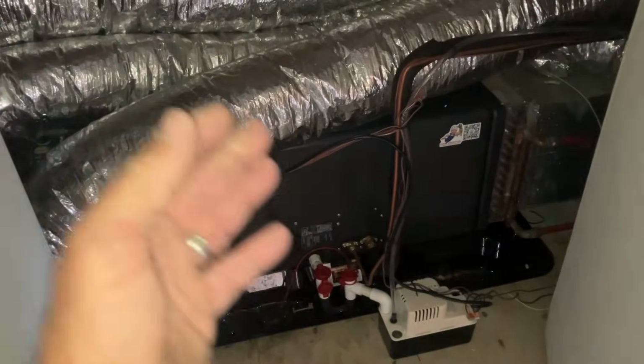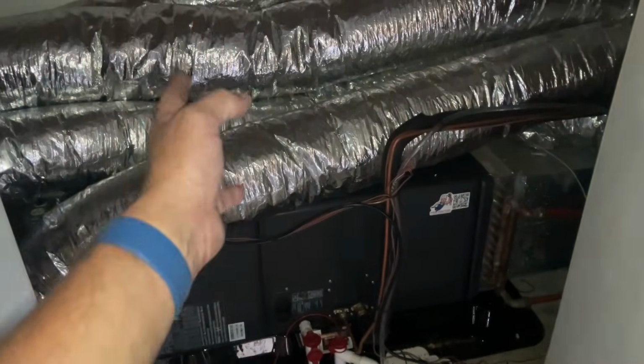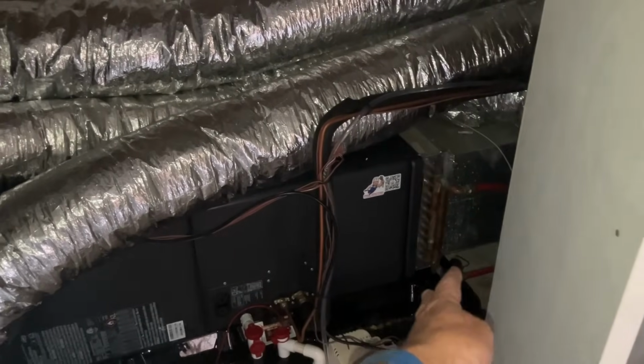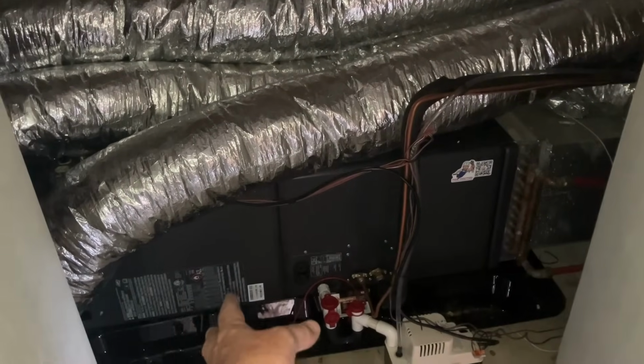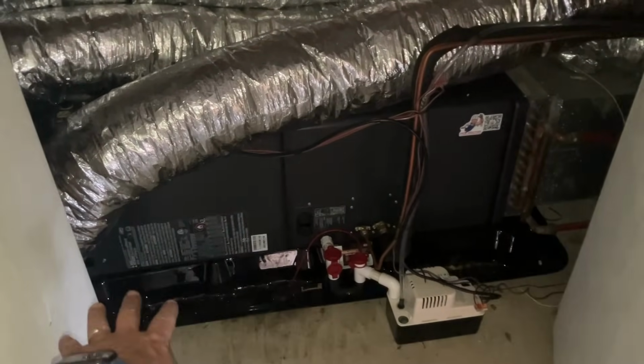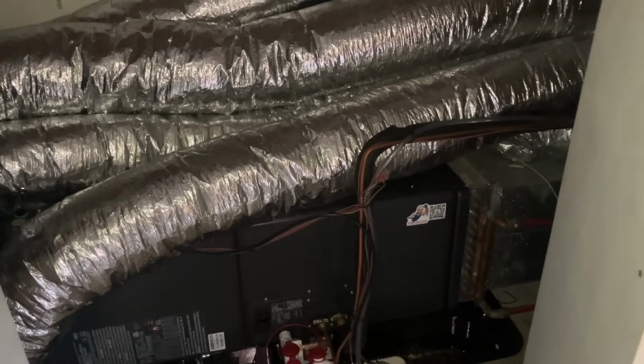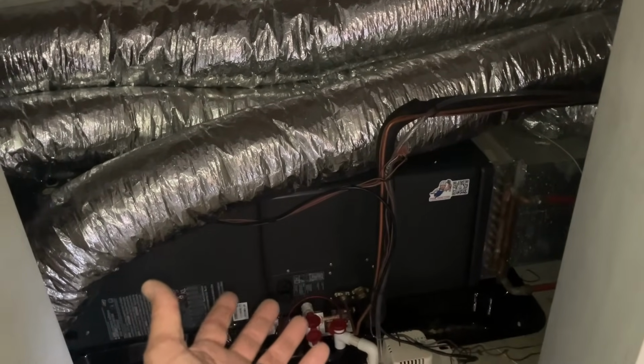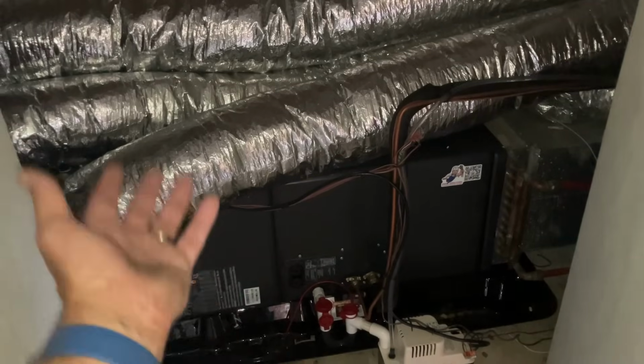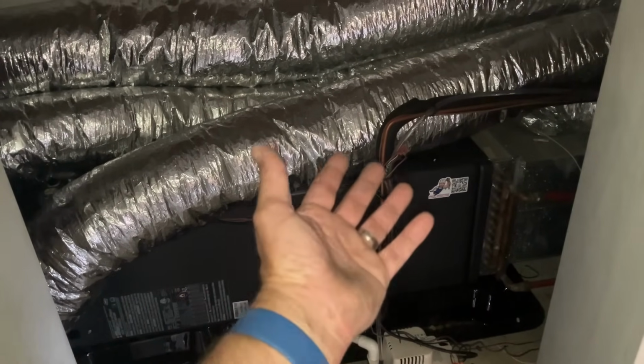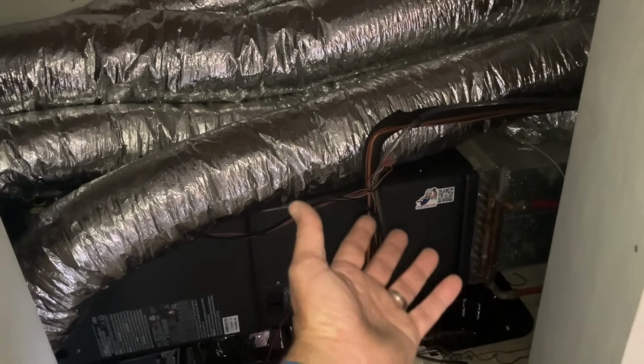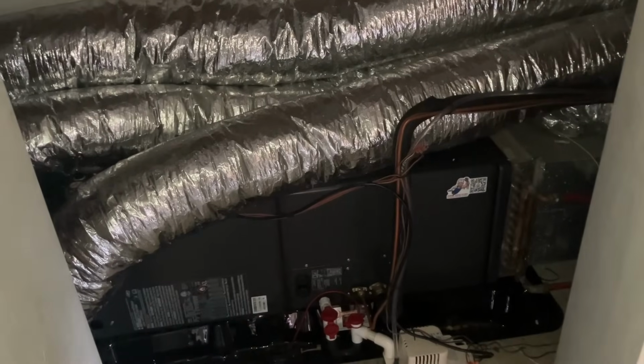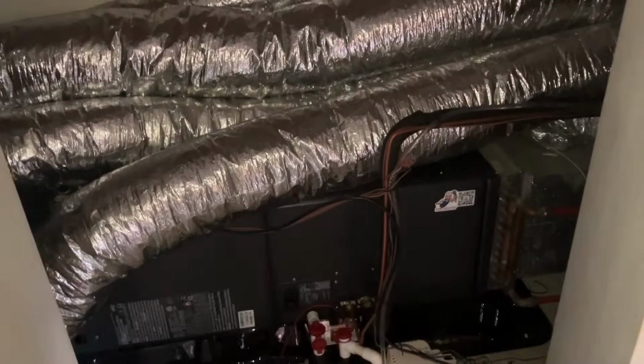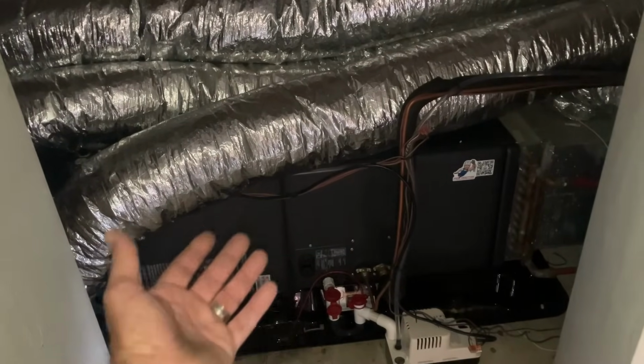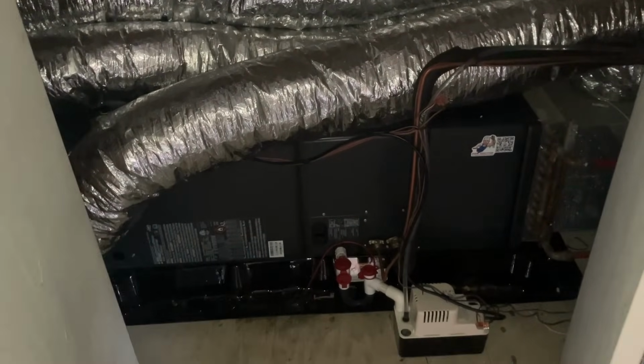Oh yeah baby. And listen, I wasn't contracted to replace ductwork or the coil. I was contracted to replace the air handler, put a new condensate pan in, and the line set, because the system has a history of leaks. And we're going from R22 to an A2L refrigerant. If it's possible and within the budget to replace the line set, let's get it done, because I'm not going to risk having leaks in the line set and telling her blah blah blah blah. You know what I mean?